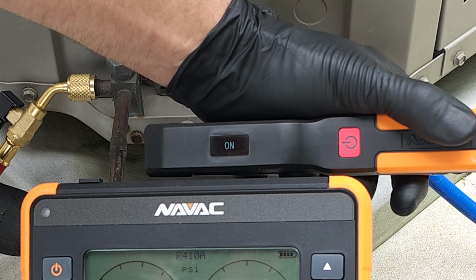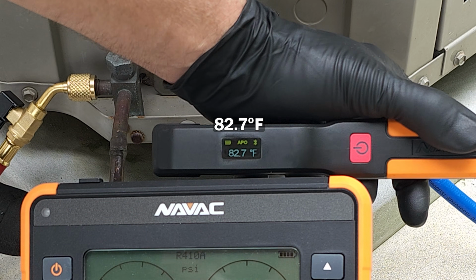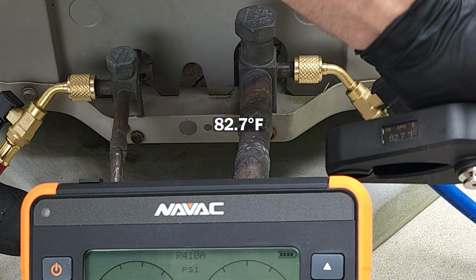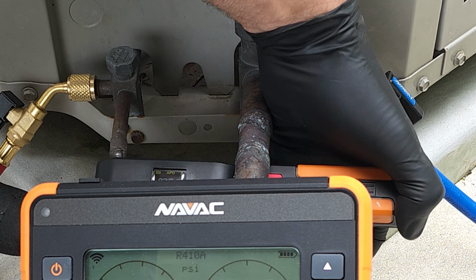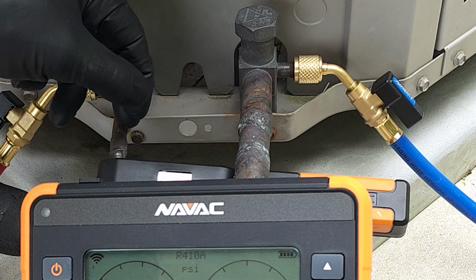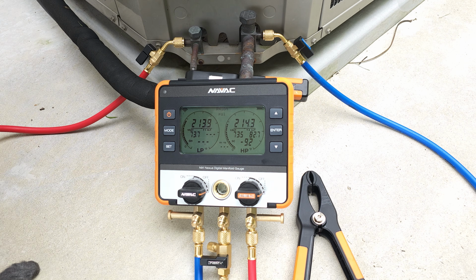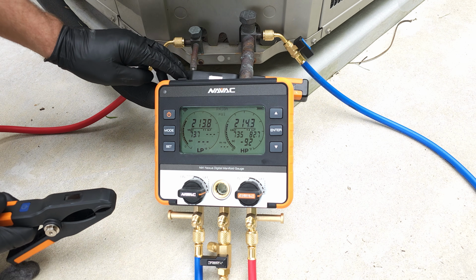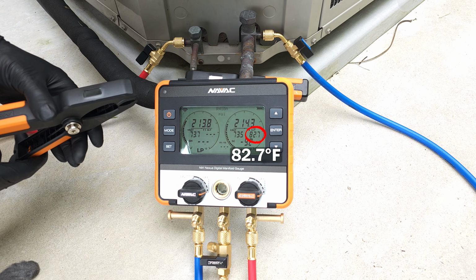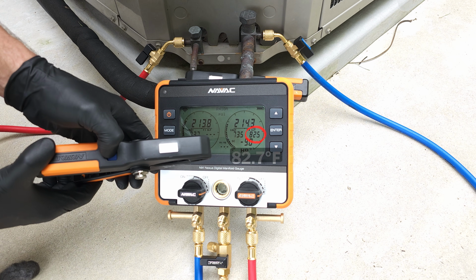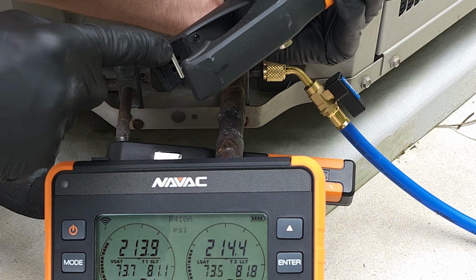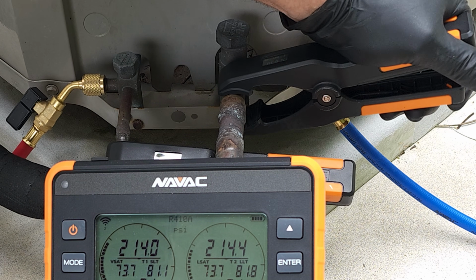We're going to take our red, and we're going to turn that on. See if you can go ahead and see the display. Right now it says 82 degrees. We're going to go ahead and connect that on right here onto the line. And so that will wirelessly connect over to here. You can see that there. And then we're going to turn this one on. Inside, there's a thermistor right here in order to measure the temperature.